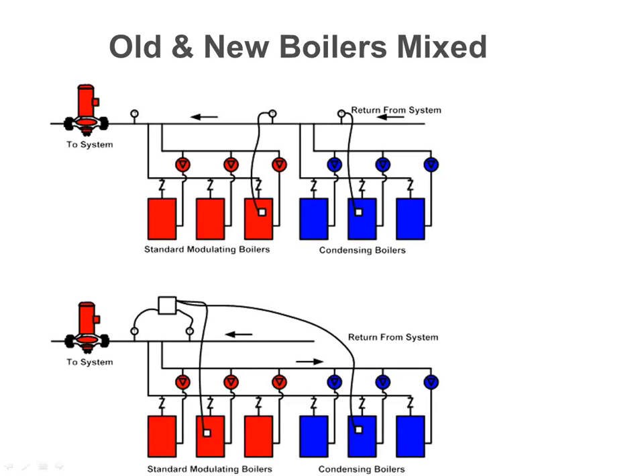If you look here on both of them, your condensing boilers are the first thing. They're taking the coldest water from that return, going through them, heating the water up. If the water isn't hot enough or sufficient, then we'll start kicking on the standard boilers. But that's only after we use condensing boilers so we can maximize our efficiencies. That's one way of piping it. There's multiple ways of piping these things.